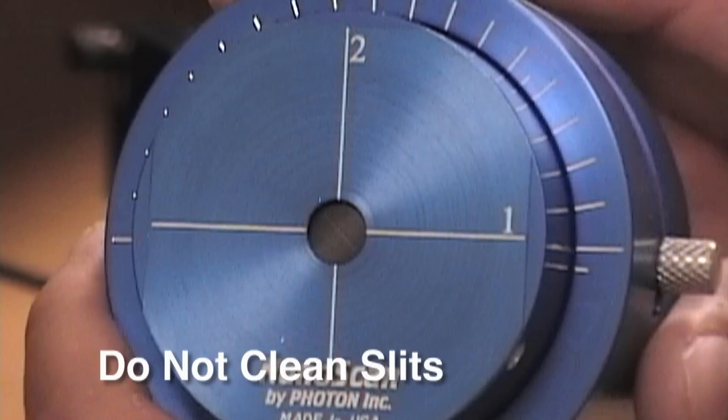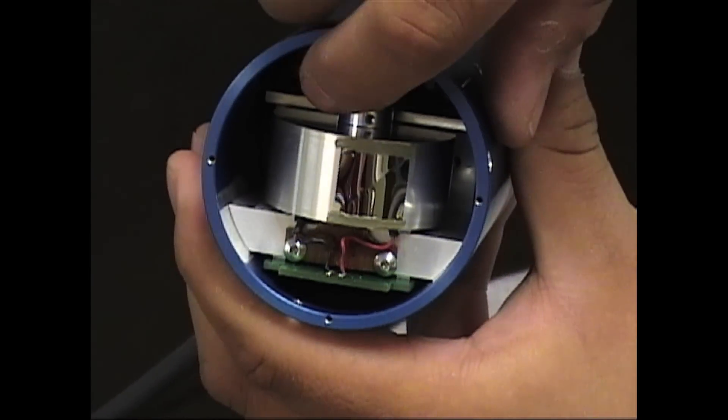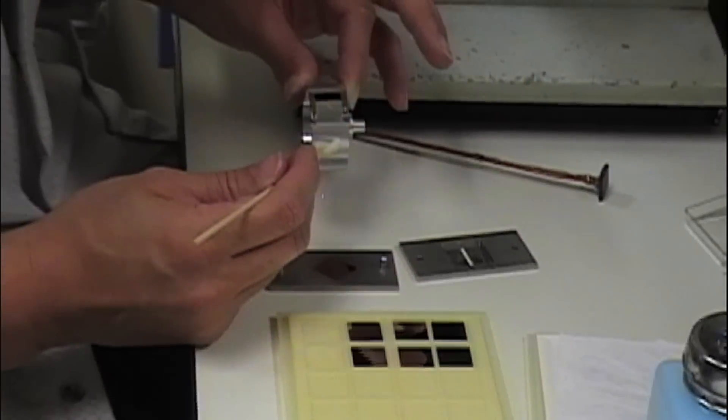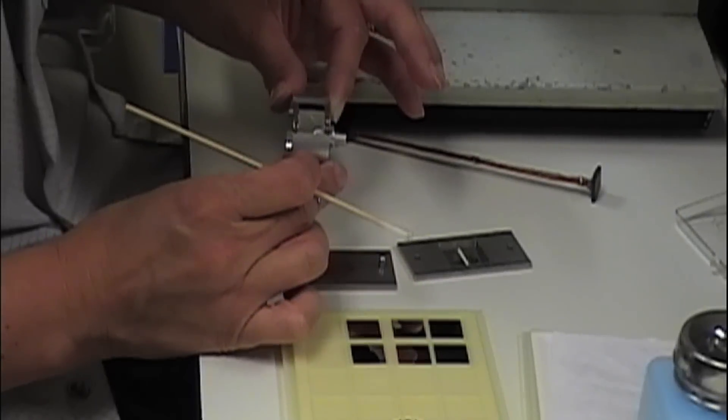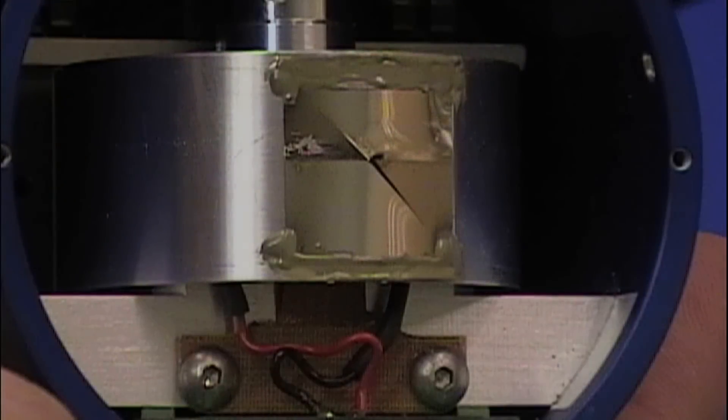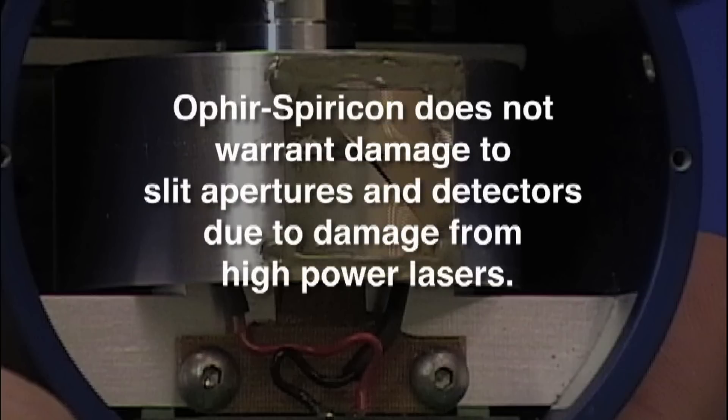Do not, under any circumstances, attempt to clean the apertures with solvents. If aperture contamination is suspected, it is recommended that the unit be returned to Ophir Spiricon for aperture inspection, cleaning or replacement, and recalibration. Ophir Spiricon does not warrant damage to slit apertures and detectors due to damage from high-powered lasers.